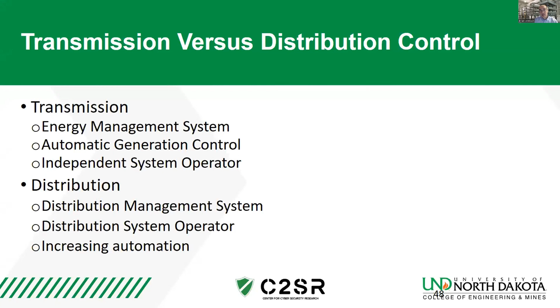So the automatic generation control will vary. It will look at frequency, and it will look at area control error, which is exported power leaving a given region. It will also look at time error. These are things that basically try to recenter the generation to keep the frequency at an ideal place. This is usually updated on timescales of seconds in a lot of regions, and this may be run at a utility control center, or it may be run at a regional operator level.